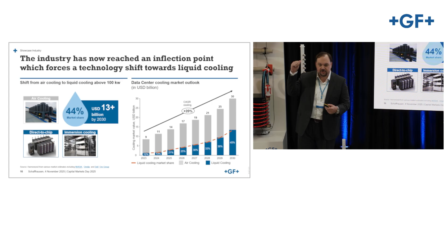Historically, as Thomas alluded to, whether it had a coil and water on it or not, the data center always had air cooling—CRAC or CRAH gallery feeding a cold aisle, which would pull air through the front of the server. Small fans would eject it out the rear to the hot aisle, and the process repeats. That's still there and will be for a long time, because you'll always need some degree of humidity control, latent heat removal, and air movement for human workers in the space. There aren't as many workers in the data center as there used to be, with a lot of automation including robots for racking and stacking.